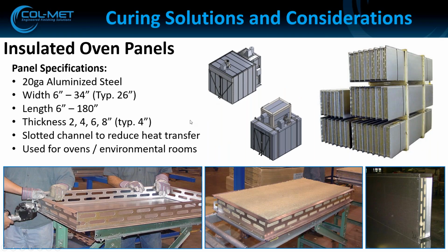I mentioned the insulated oven panels. Col-Met manufactures in-house all of our own oven panels. These ship out completely assembled. They're 20-gauge aluminized steel, common width 6 to 34. We typically base the design of the oven around a 26-inch design, which gives you an inch of flange on each end, so you have a working length of 24 inches. They can be made from 6 to 180 inches long, depending on the type of oven. The standard thickness is 4 inches, but we can also make them thicker.